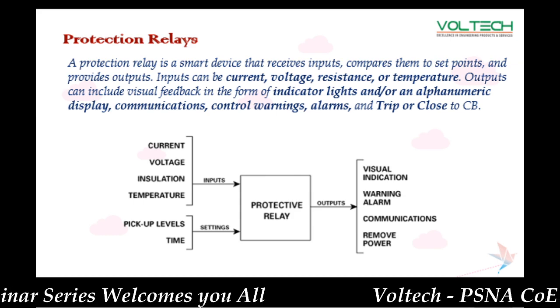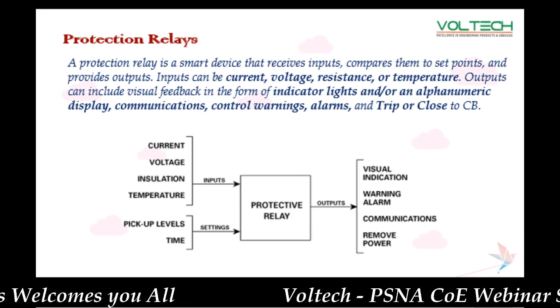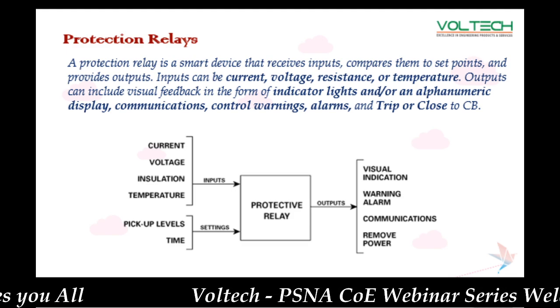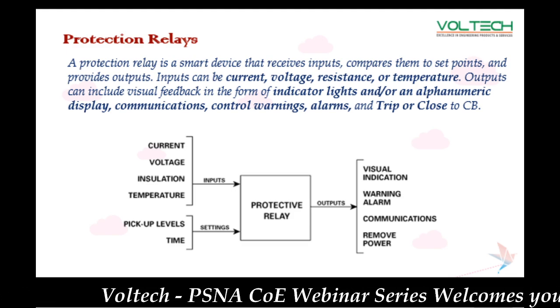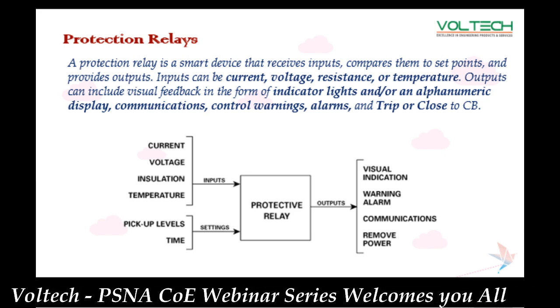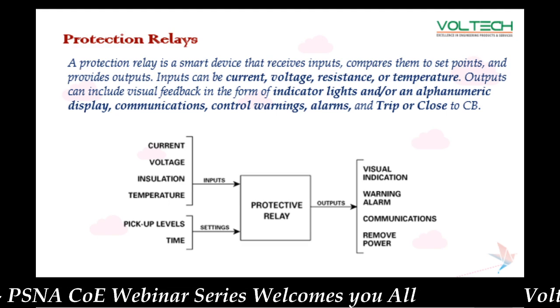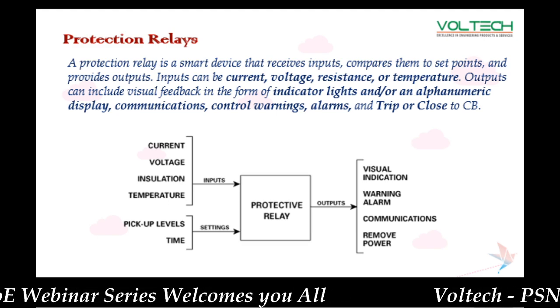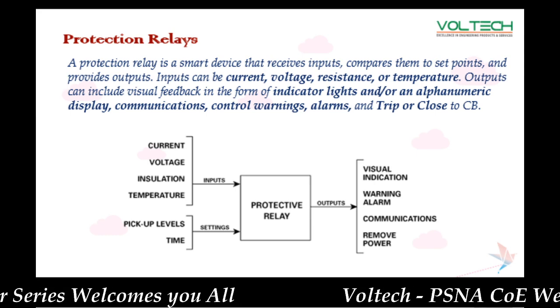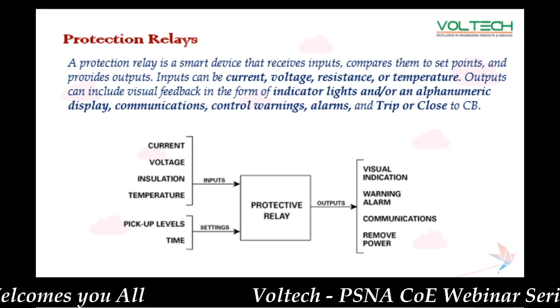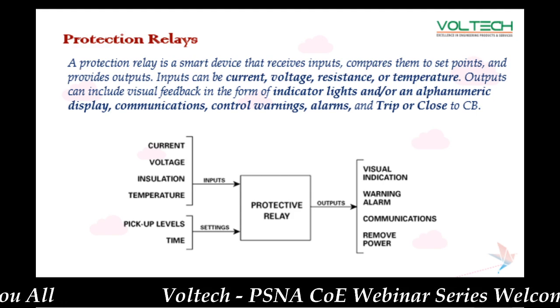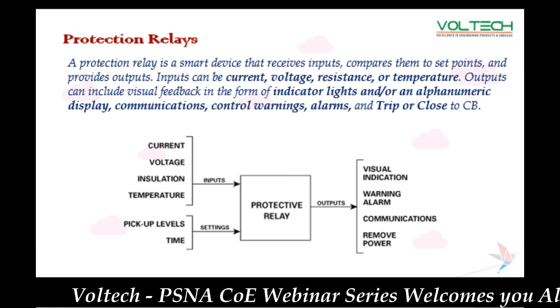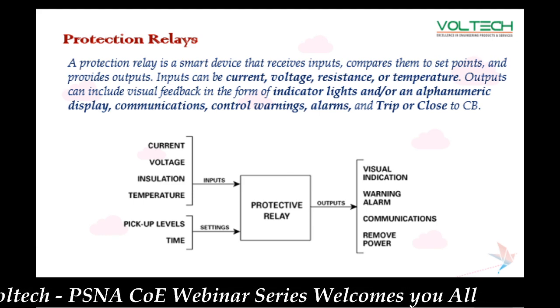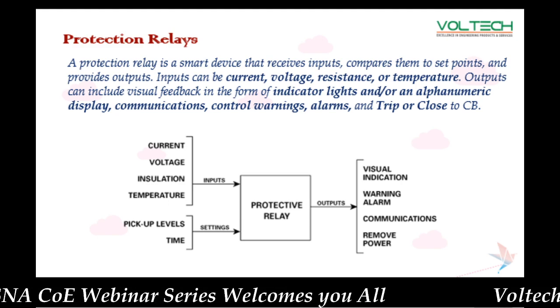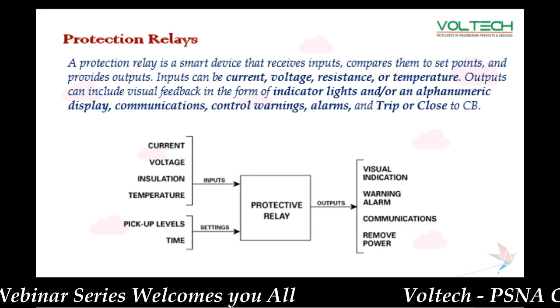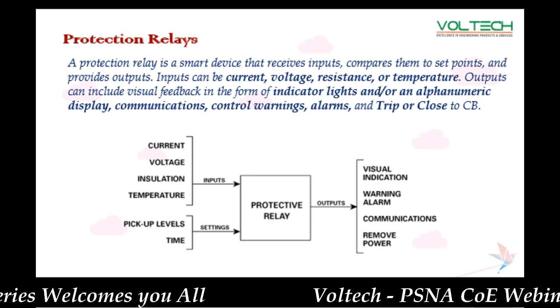The input can be current, voltage or insulation temperatures, different types of inputs are available, and the settings are pickup levels or time. Pickup level means we have to give the range for the current, how much the current should be. We should limit the current, so we should not allow the current to flow beyond that, so we can give the limitations here. The time is how long I have to allow this much current. Everything is given to this relay, and the protection relay will give the output as a visual indication, a light or alarm, communication or remove power. It's simple. An alarm means it shows in the relay itself.